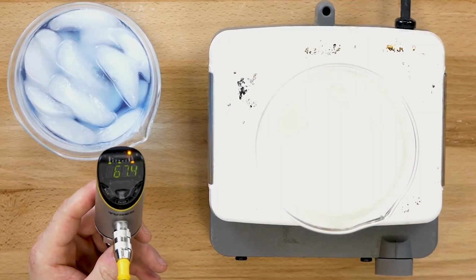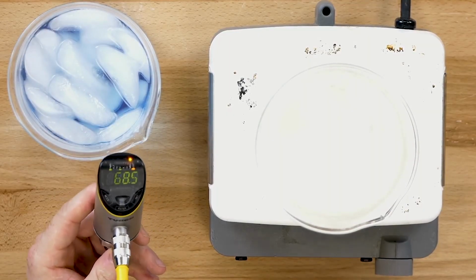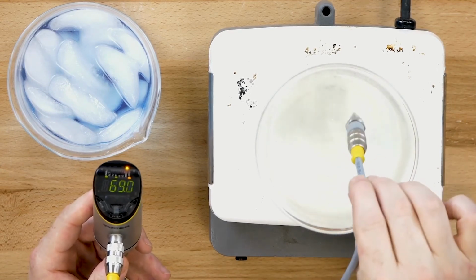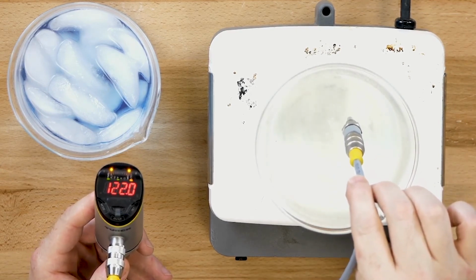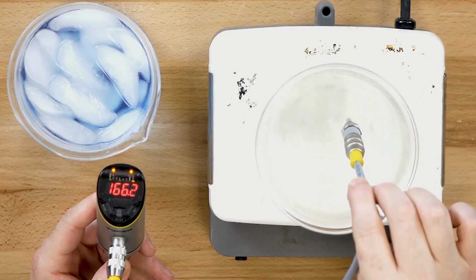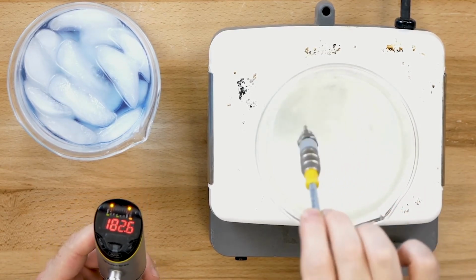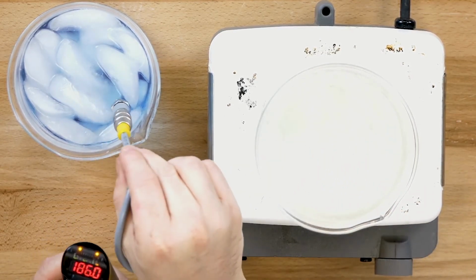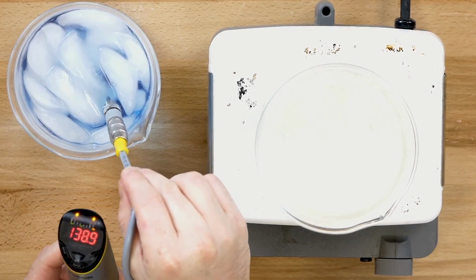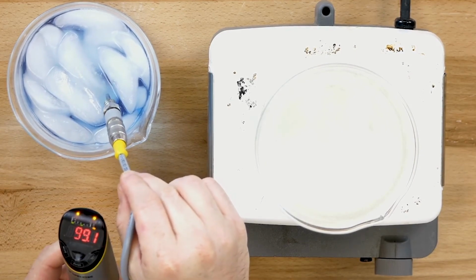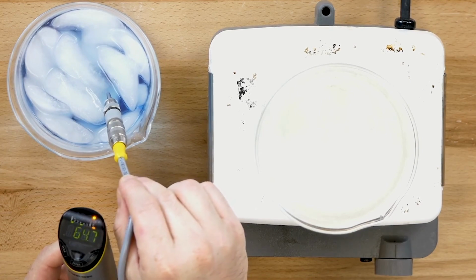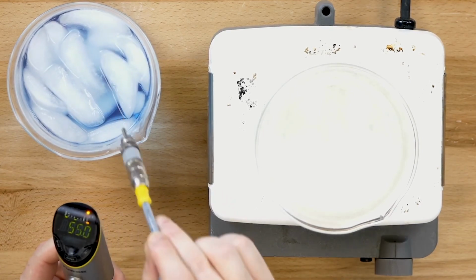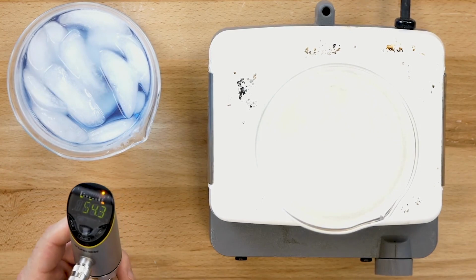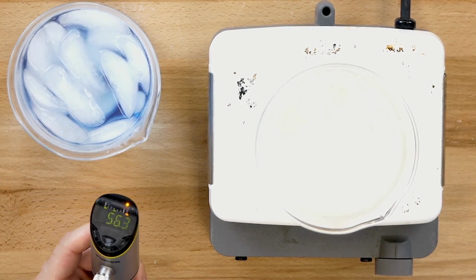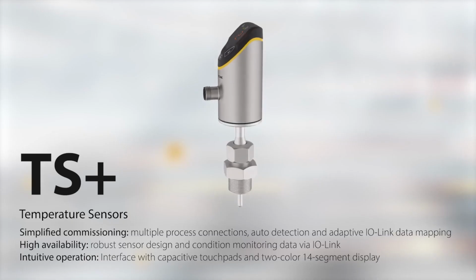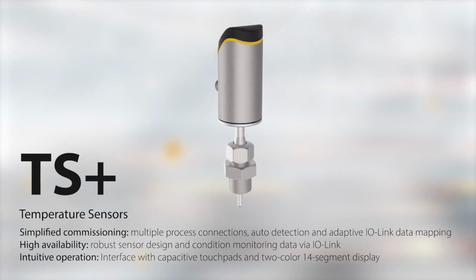Let's test the sensor programming with the test box. As you can see, once the temperature rises above 80 degrees Fahrenheit, our PNP output alarm turns on. Additionally, when the temperature comes back down within that limit, the LED screen is going to change from red back to green. It's important to note that this is an IO-Link sensor and it can also be programmed via IO-Link. Easy commissioning and high plant availability. That's TS Plus.